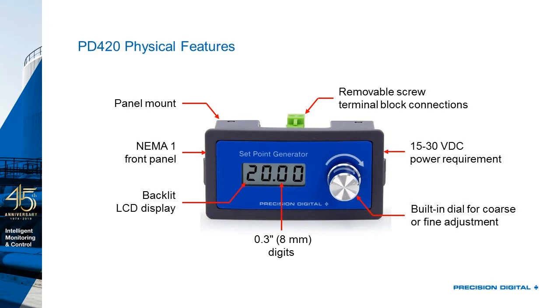And as with most precision digital products, there's a depluggable connector on the back. So doing your wiring of this is going to be pretty easy. And it's only 2 wires, as it's a loop-powered signal generator. That loop can be 15 to 30 VDC powered. So if you are like most people and you're using a 24-volt supply to run your 4 to 20 milliamp loop, you've got no problem there. And we've got a dial on the front, which is what you use to adjust your 4 to 20. That means you don't have to dial in specific numbers with like an up, down, left, right keypad. You just spin the dial to what you want.